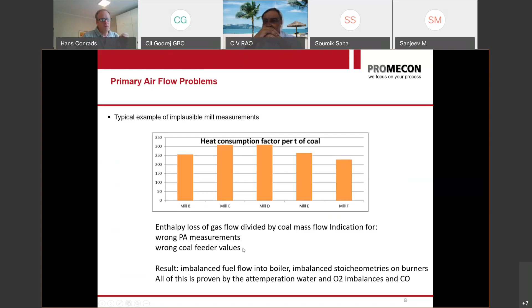You either have wrong primary air values, or you have wrong feeder values, or both values are wrong. You have wrong feeder and wrong primary air. That's what I usually find in power stations. And the result is that you have a wrong fuel input into your boiler. So that's one important finding. And if you go to your power station, you will find a very similar thing. Now, the second thing that we find frequently, your primary airflows are simply wrong.